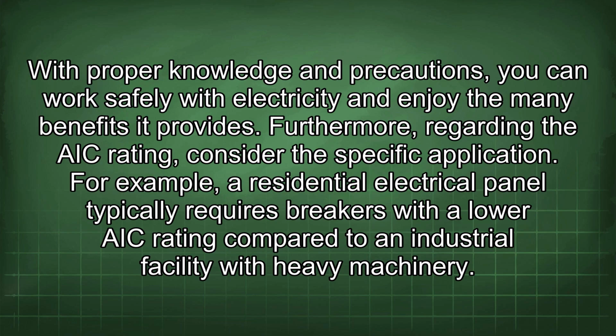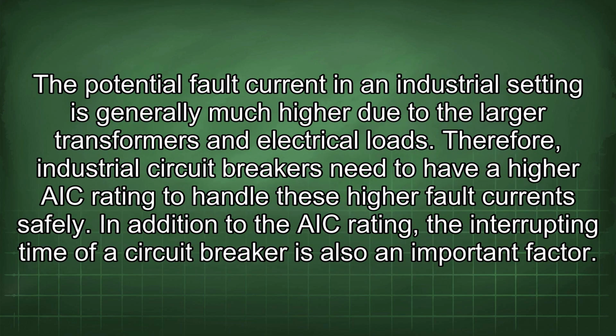Furthermore, regarding the AIC rating, consider the specific application. For example, a residential electrical panel typically requires breakers with a lower AIC rating compared to an industrial facility with heavy machinery. The potential fault current in an industrial setting is generally much higher due to the larger transformers and electrical loads. Therefore, industrial circuit breakers need to have a higher AIC rating to handle these higher fault currents safely.